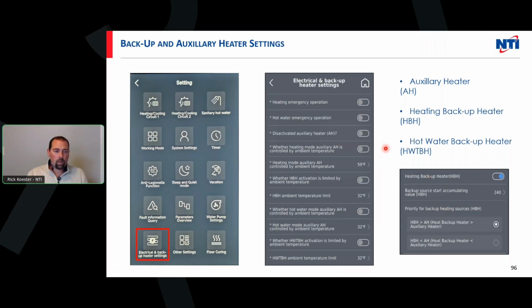This will be a big player for us when it comes down to hybrid systems, right? Electrical and backup heater settings. So here we can turn on, do I want it for heating? Do I want it for hot water? Do I want to deactivate the auxiliary heating? Priority switching, as you can see down here, if I do heating backup heater and I activate that, this is going to be basically a start time. This down here is going to be my priority. This is going to tell me which one. Do I want to activate my auxiliary heating before I do my heating backup, or vice versa? So you have all of that right here, right from that screen. So we'll see this a lot.